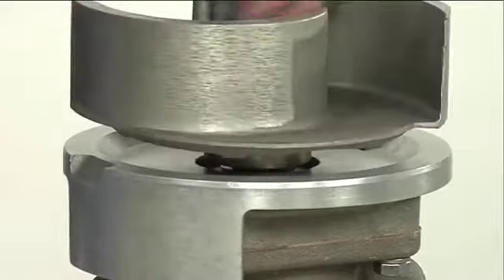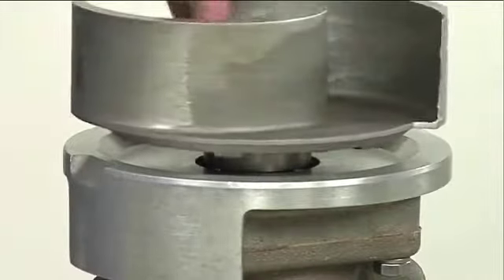A firm resistance will be felt as the impeller presses the stationary seat into the seal plate bore. As the stationary seat becomes fully seated, the seal spring compresses.